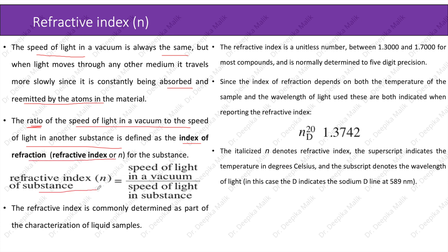The formula is given here. The refractive index is commonly determined as part of the characterization of liquid samples. The refractive index is a unitless number between 1.3000 and 1.700 for most compounds and is normally determined to five digit precision. Since the index of refraction depends on both the temperature of the sample and the wavelength of light used, these are both indicated when reporting the refractive index.